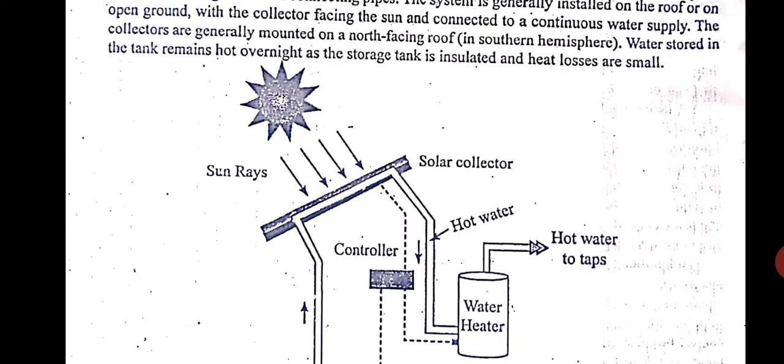The water stored in the tank remains hot overnight as the storage tank is insulated and the heat losses are small. So you can see the sunlight is falling on the flat plate collector. Cold water is supplied continuously - this is wrong actually, it doesn't, it is not supplied. For a house, there will not be a pump. The pump will supply the water to overhead tank and from the overhead tank due to gravity it will flow to the flat plate collector. After getting heated it comes to the storage tank, this vertical tank which is shown here.